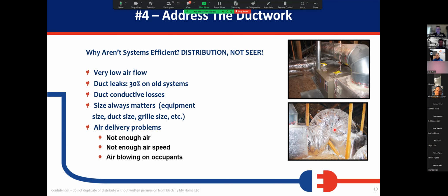Equipment nowadays is way more susceptible to high static pressure than it used to be, especially if you're installing low NOx furnaces. We know those things are really, really touchy. They need to have the right amount of air going through them. They burn extremely hot, so it is really important to get the right amount of airflow. So increase return air sizes and pay attention to the ductwork. If you've got a massive amount of uninsulated ductwork in the attic space, there's a lot of thermal loss we're going to get through this. So really just pay attention to this. This is the big deal.